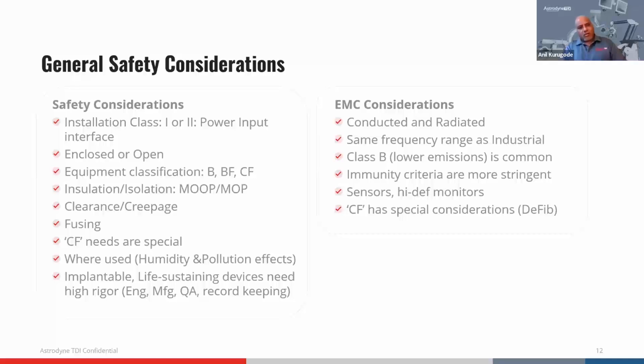Fundamental to all safety and medical products is the long-term damage of insulation. For example, we start today and it's all brand new, it looks like it passes all the testing, more than meets the requirement. But what if it's sitting in a closet for a couple of years and humidity and a little bit of local pollution has crept into the design, into the product, and degraded the insulation? Think about it, you provide a certain two layers of insulation and something else happens around it and compromises that. So what do we do about it?